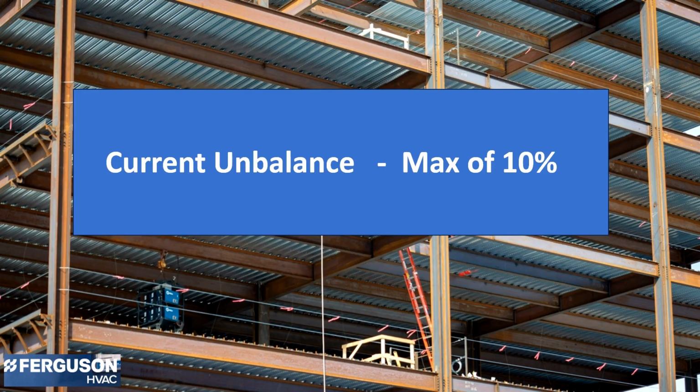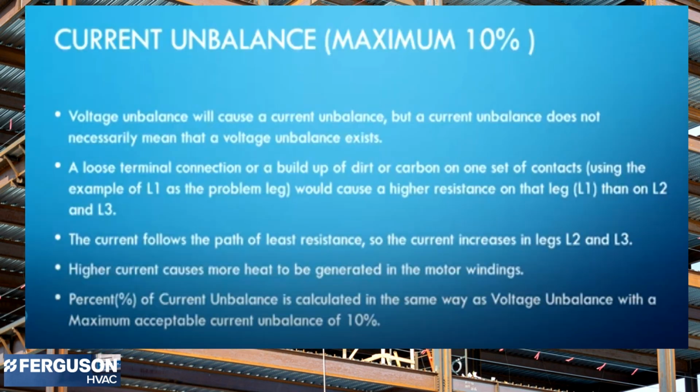The other thing you need to look at is the current unbalance, which you can have a maximum of 10%. Voltage unbalance will cause a current unbalance, but a current unbalance does not necessarily mean that a voltage unbalance exists.